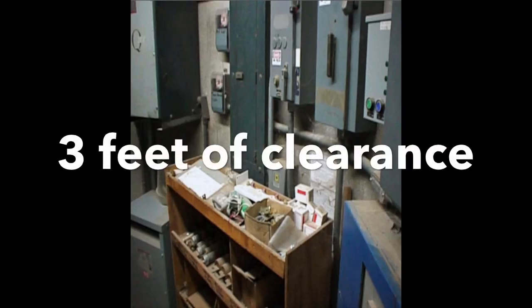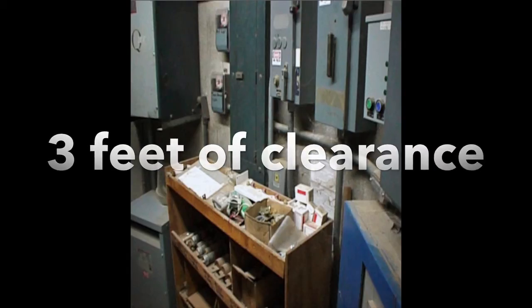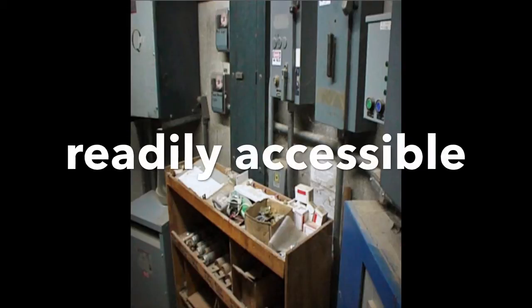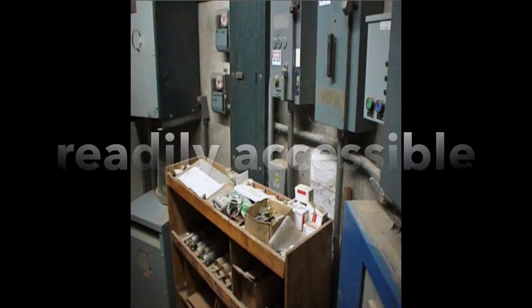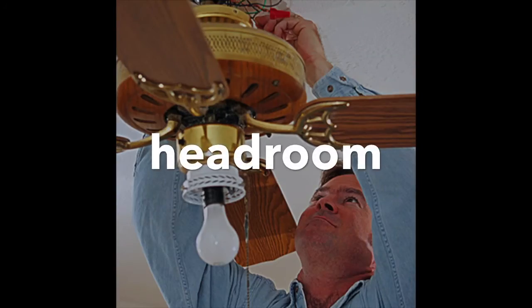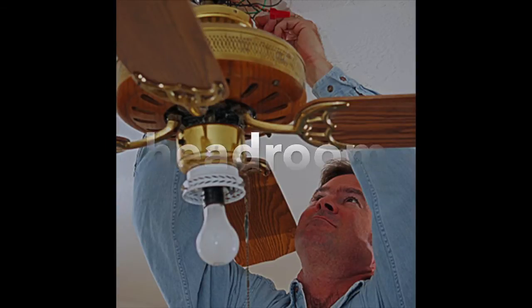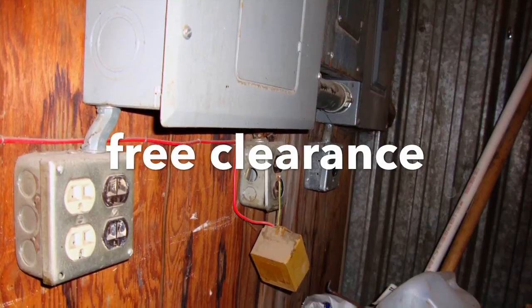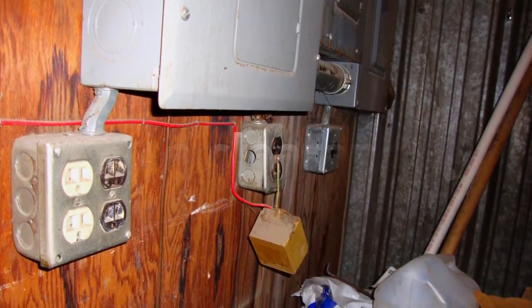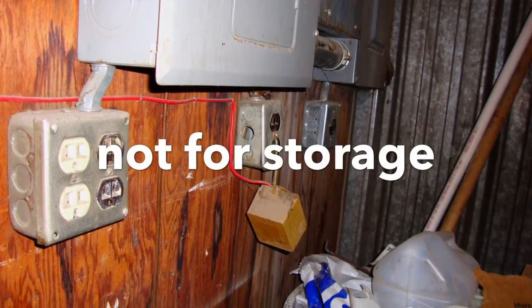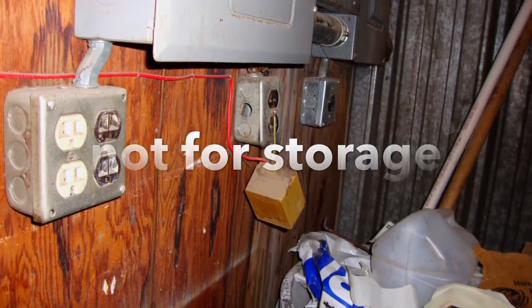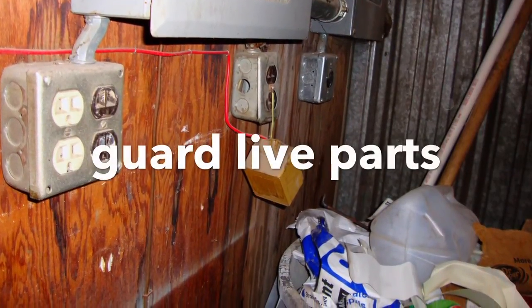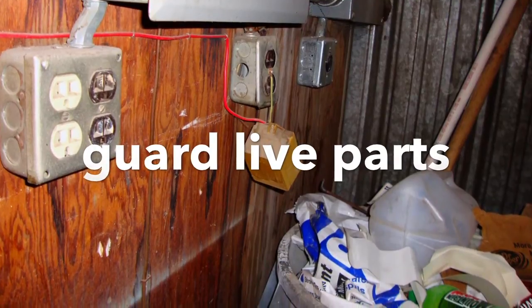Is there 3 feet of clearance in front of these electrical panels? Electrical equipment will always be readily accessible. If the equipment exceeds 6.5 feet, the headroom is the height of the equipment, and you must always maintain a clear space around the equipment. The working space around the electrical equipment may not be used for storage, and when live parts are exposed within the equipment, they shall be guarded.